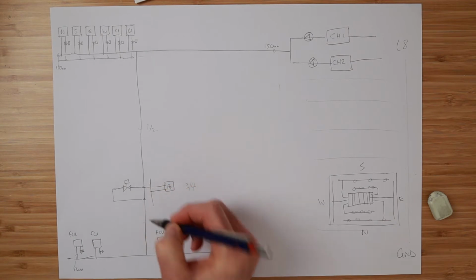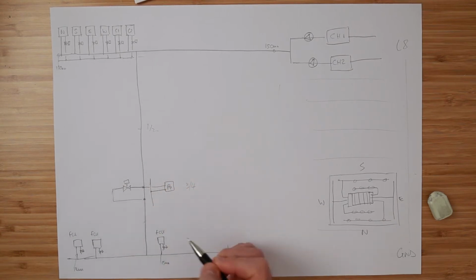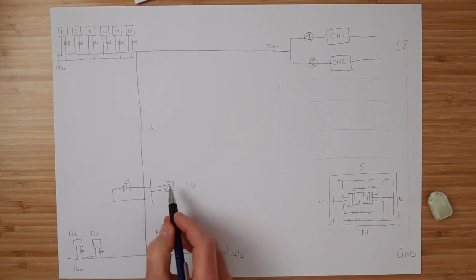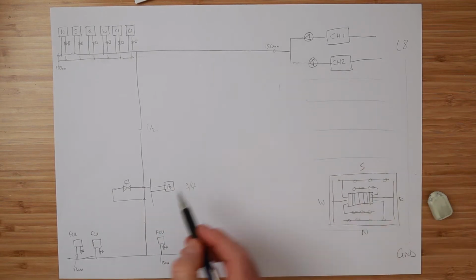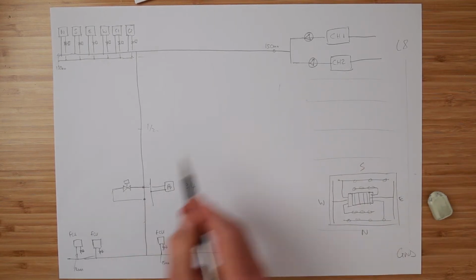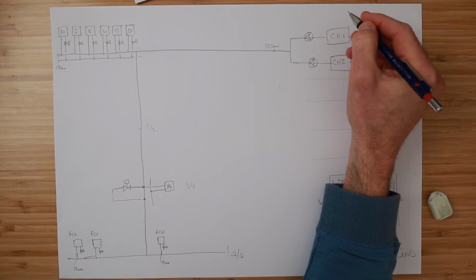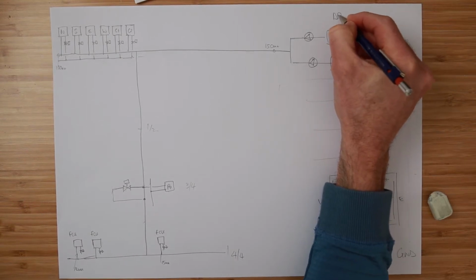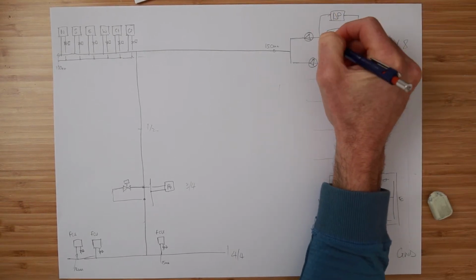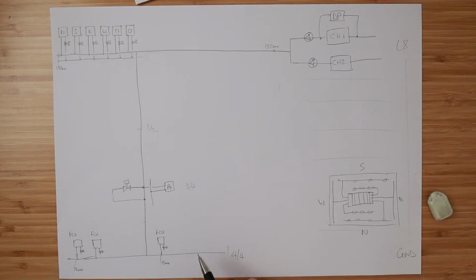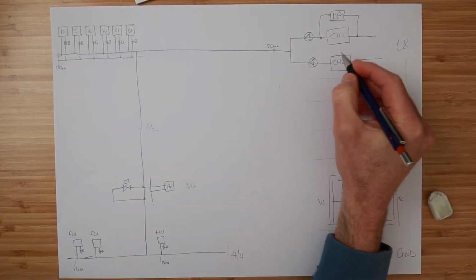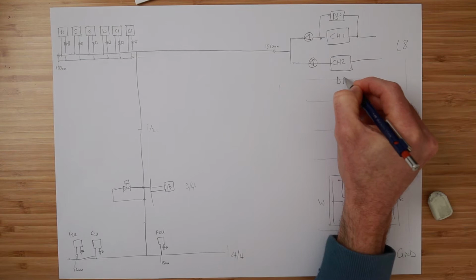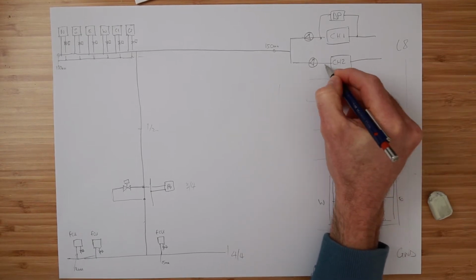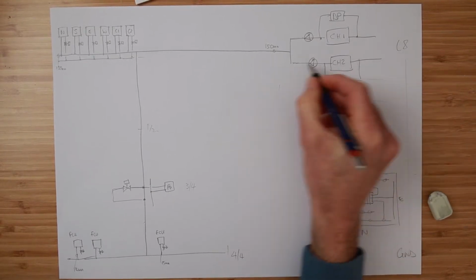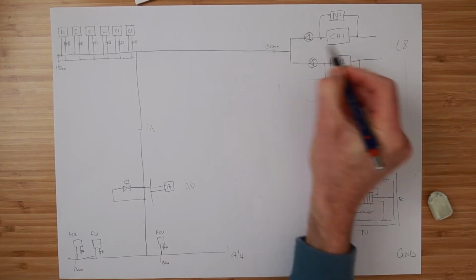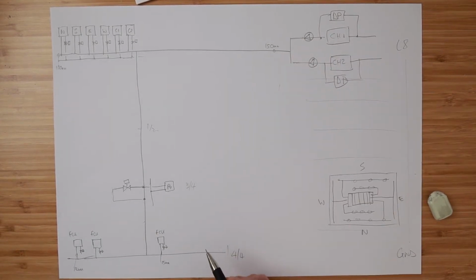So that's supposed to be a flow and return. It's not very clear, I guess. So here's our system pressure transmitter controlling the speed of the pumps. Here's our bypass valve controlling the minimum flow through the evaporator. So there's our differential pressure transmitter across the chiller. Probably got one this side too. Not probably, there would be one this side too. Could have flow meters over here. We're going to have pressure transmitters for this example.